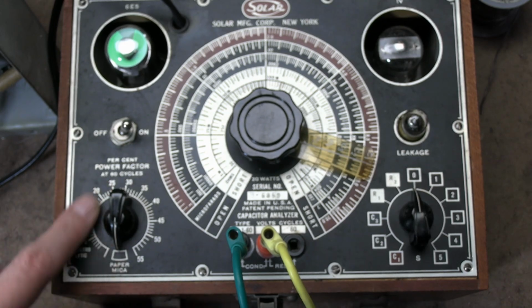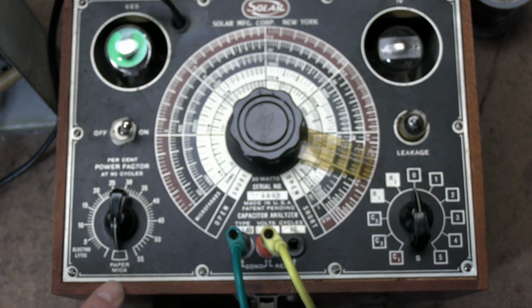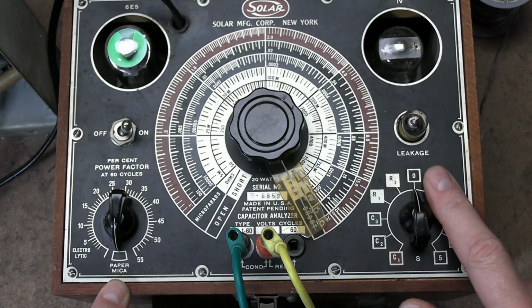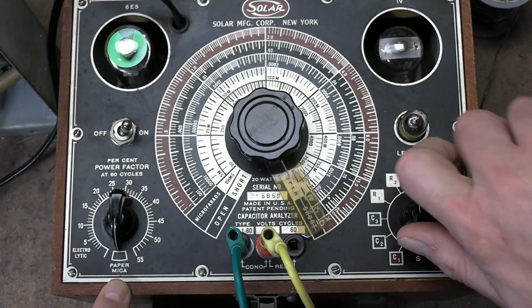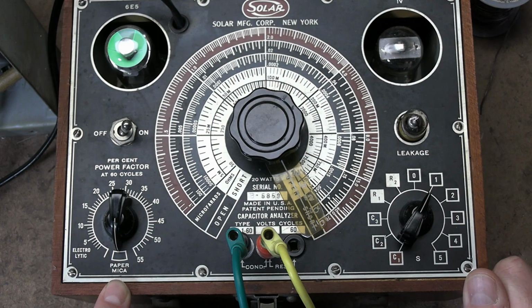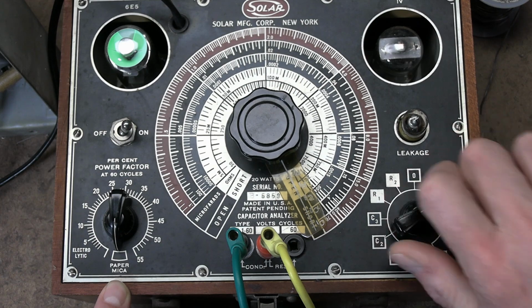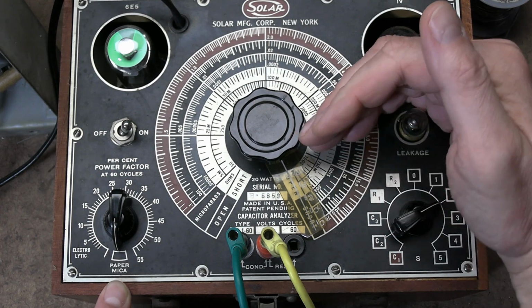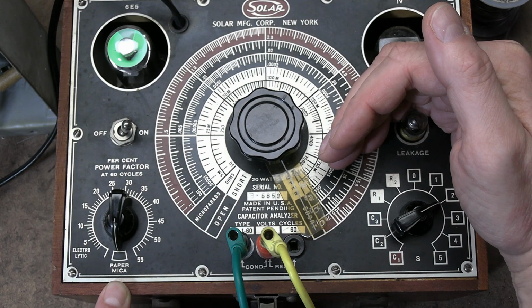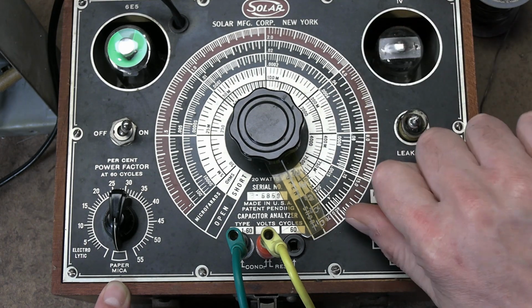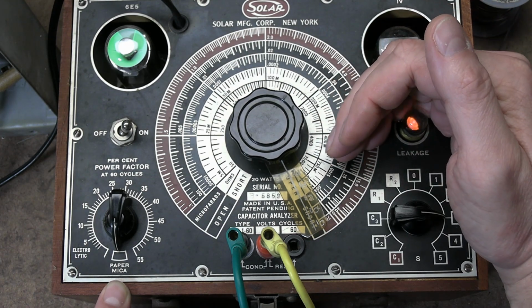Okay, set our capacitor type to paper or mica. Get this clockwise - you check for leakage first. Go to 100. Seems to be okay. At 200 - uh-oh, it's flashing already. 300 - it's flashing like crazy.